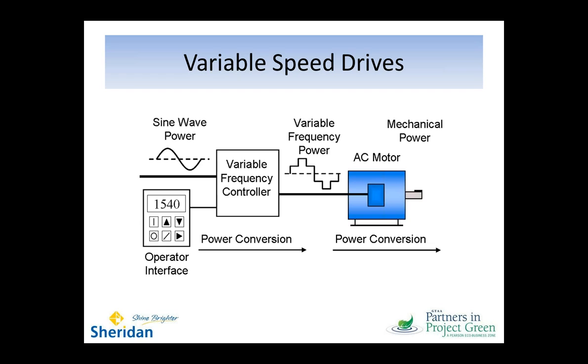But just talking about variable speed drives, the idea is really fairly simple. An AC motor is kind of a dumb hunk of metal, and if it sees a certain input frequency, it'll spin in relation to that. So if you slow down the frequency of power coming in, it'll slow down too. The whole idea of the variable speed drive, the electronic controller on the feed side, is to take the 60 hertz frequency that's coming in and change its frequency. And in so doing, it changes the motor speed.